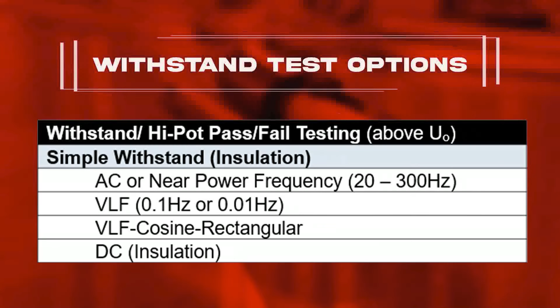Now, remember, he said he had 15 kV and 35 kV cables. Is that what we're talking about here? Mostly what we're talking about here is medium voltage shielded cables, anywhere from 2.4 kV all the way up to 69 kV. That's the typical cables we're talking about in an industrial environment. So what we're trying to do when we go to perform maintenance or testing on that main insulation system is trying to find those weak spots. And withstand testing is one of the easiest ways to do that. It's the most cost effective, I would say.